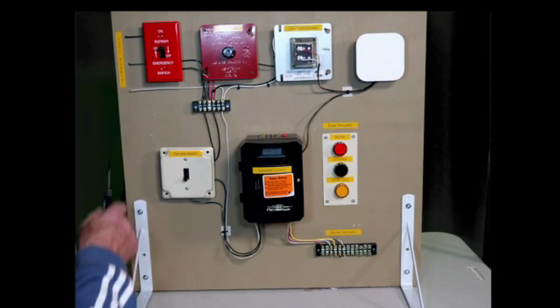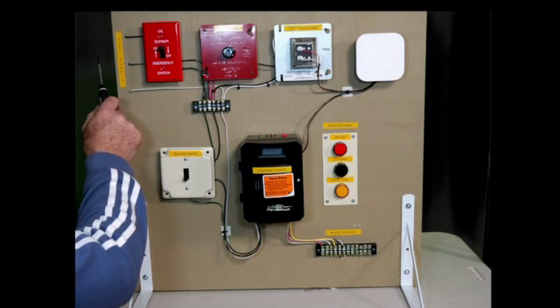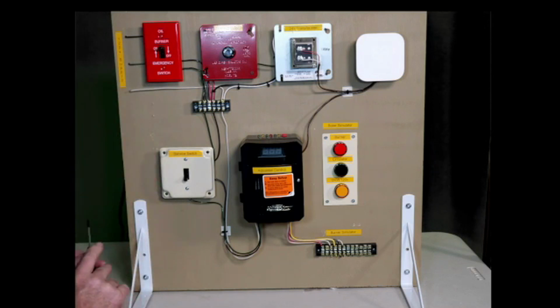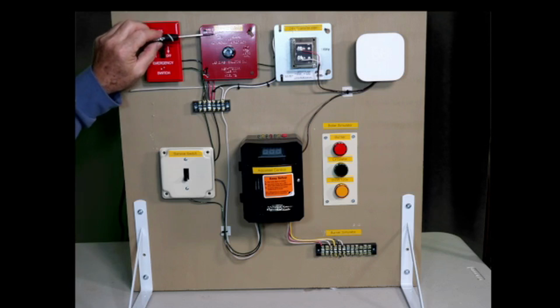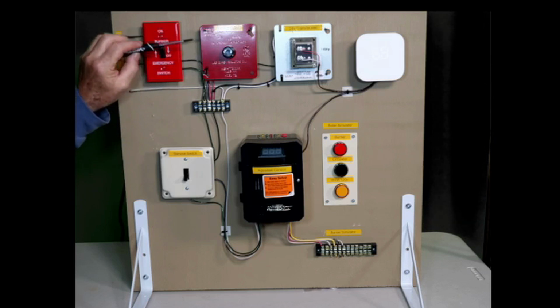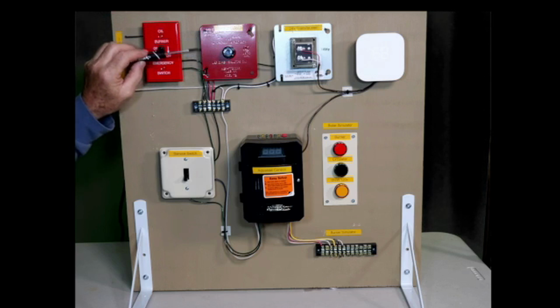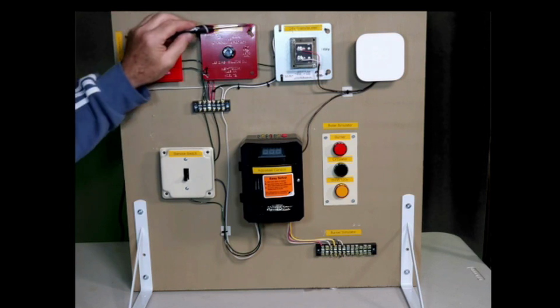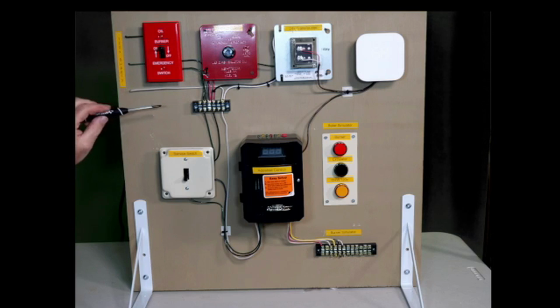So the power comes in from the circuit breaker panel, and if this is a newer installation, it's going to feed a remote emergency switch, sometimes located at the top of the basement stairs or on a wall in the living space of the home. And from the emergency switch, it's going to come into a junction box above the boiler containing a thermal cutoff. And oftentimes from that thermal cutoff will branch into a power transformer or other devices associated with the boiler.